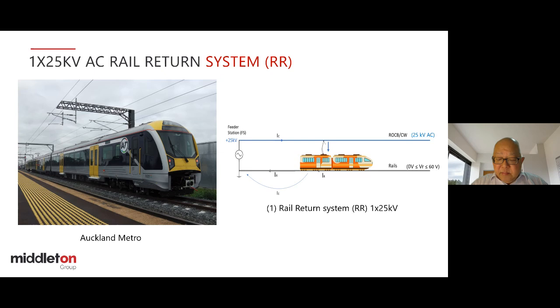50 Hz leakage current can be high, up to 20%, depending on your track form insulation resistance level. If you have very good track insulation, you will minimize your leakage. And the EMC performance is not as good compared with booster transformer and auto transformer systems.